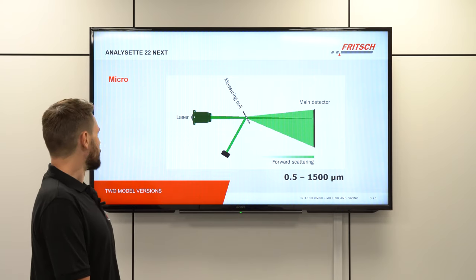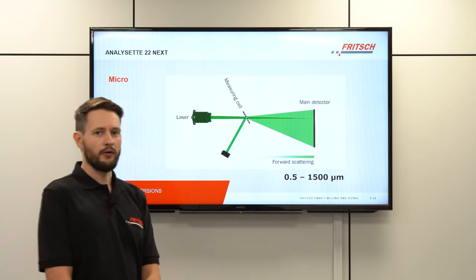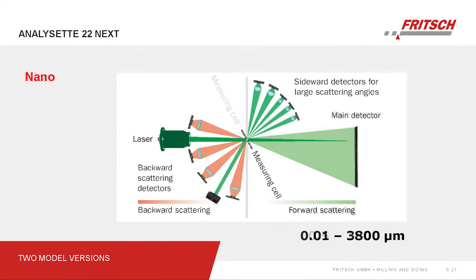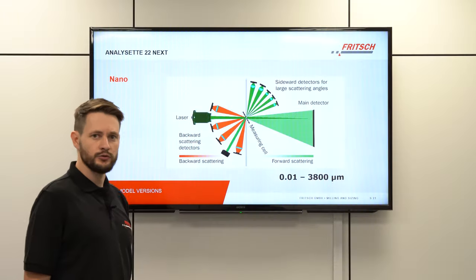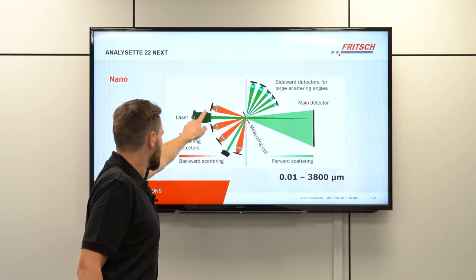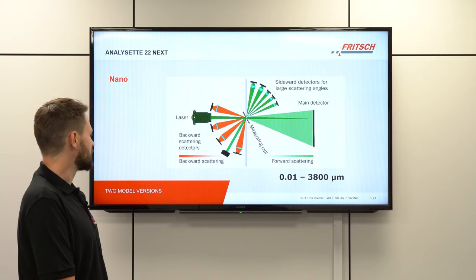On the bottom we find a monitor diode that constantly checks laser output power by the reflection of the laser at the measuring cell. In the full-blown version, the Analysette 22 NEXT NANO, there are additional detectors — 5 detectors responsible for detecting large scattering angles, and 4 additional detectors for backward scattering, which decrease the lower measurement limit to around 10 nanometers.